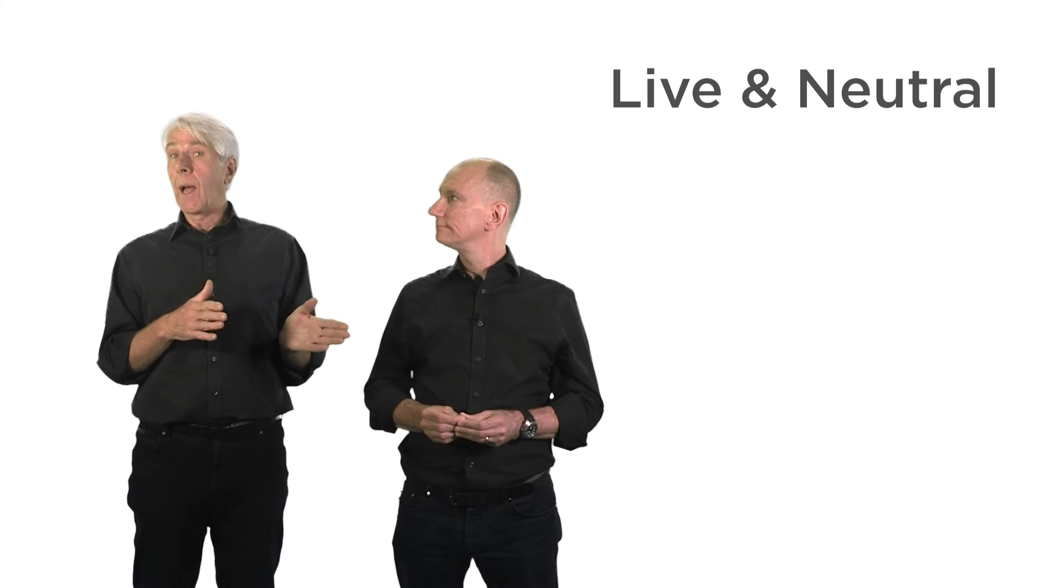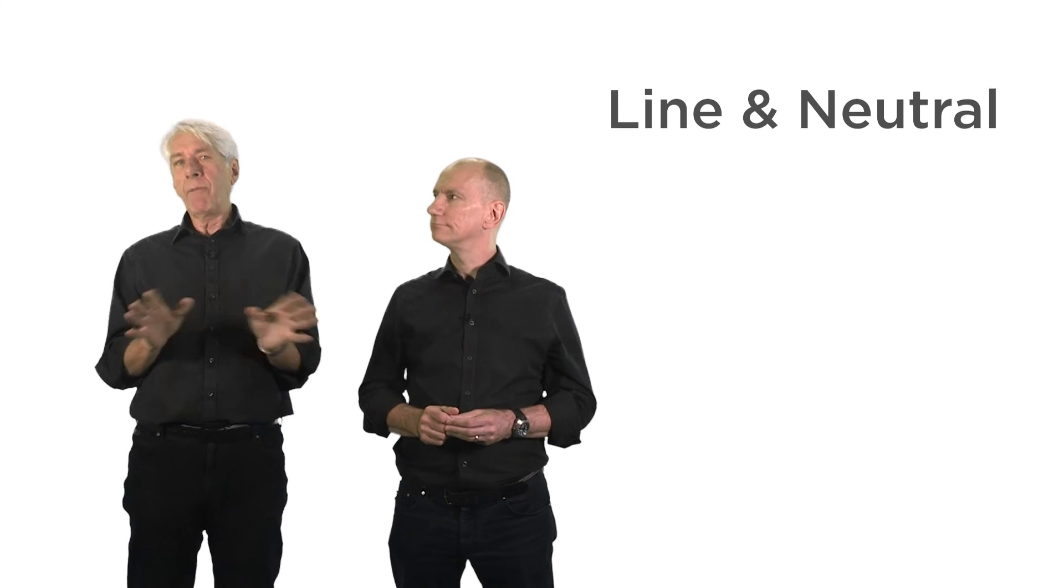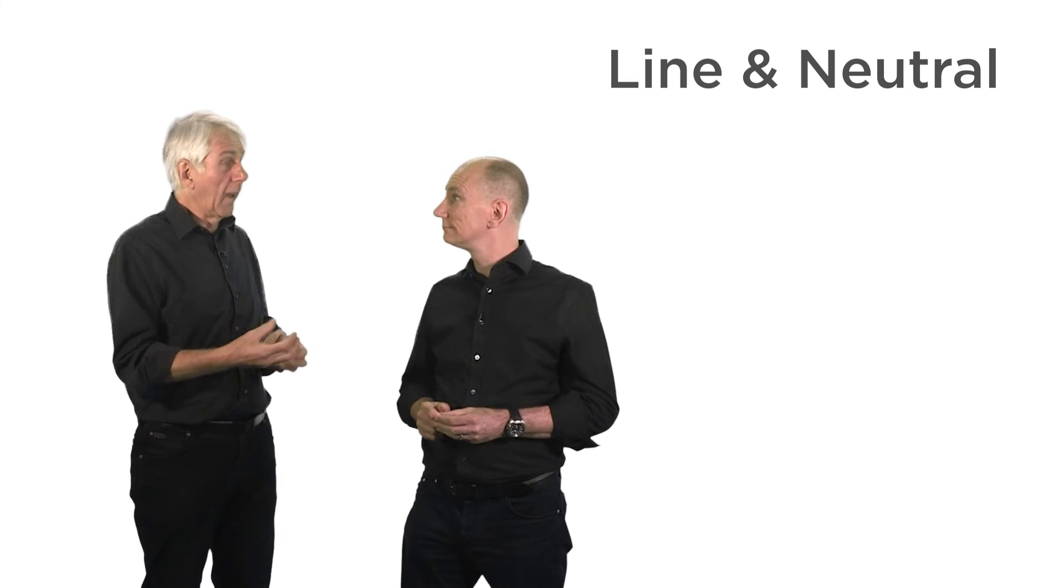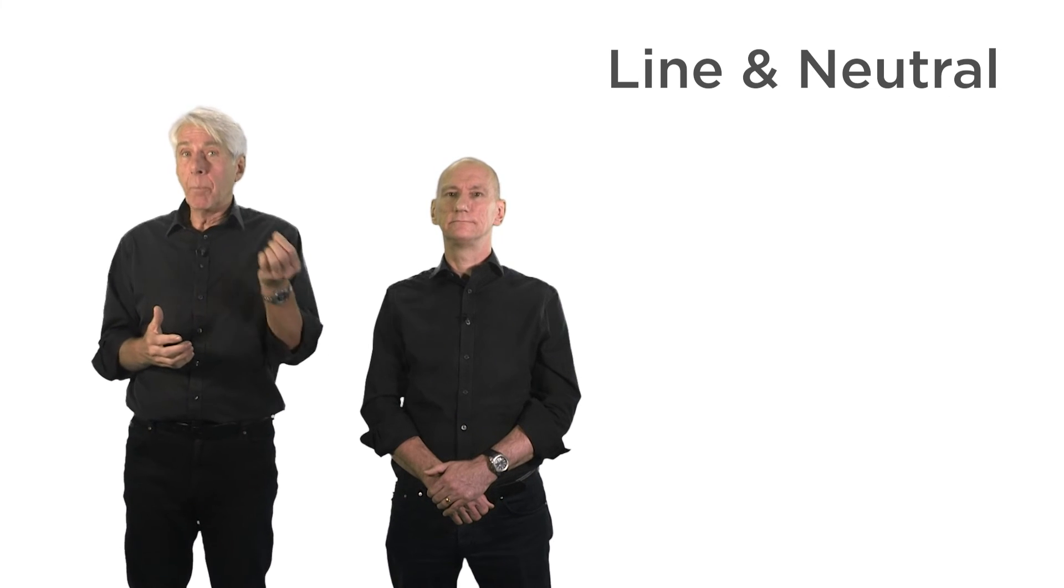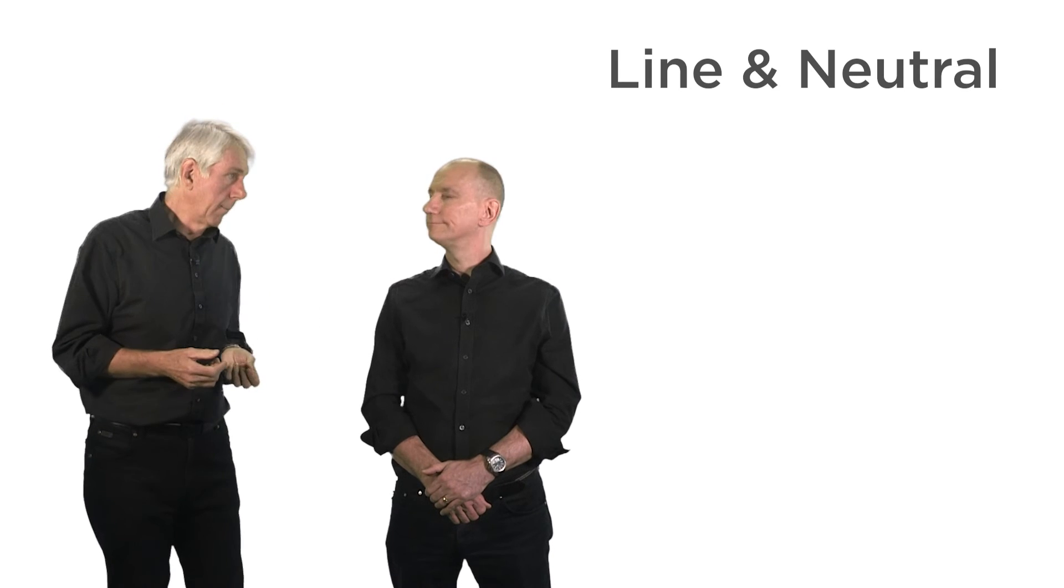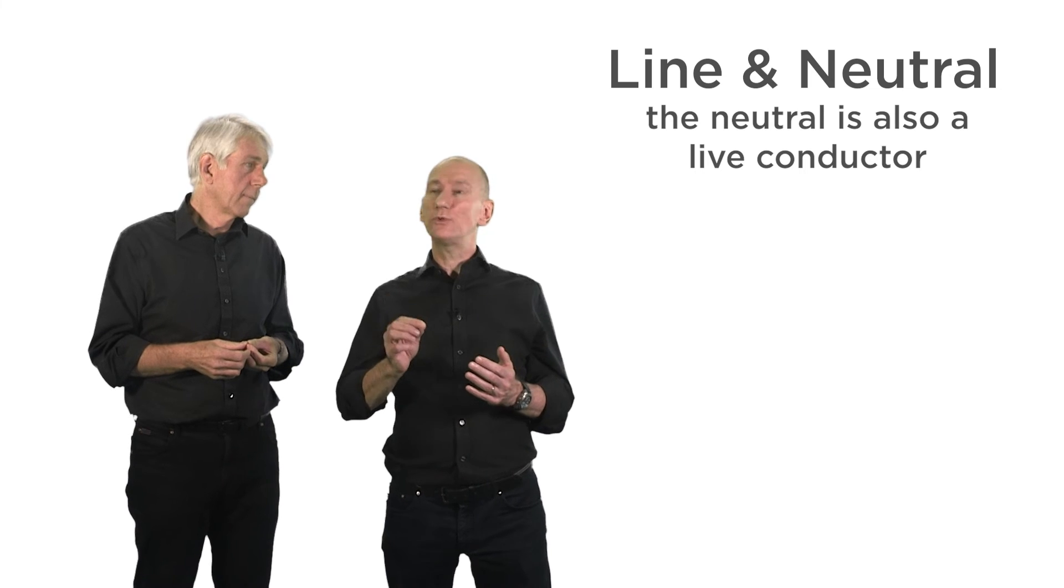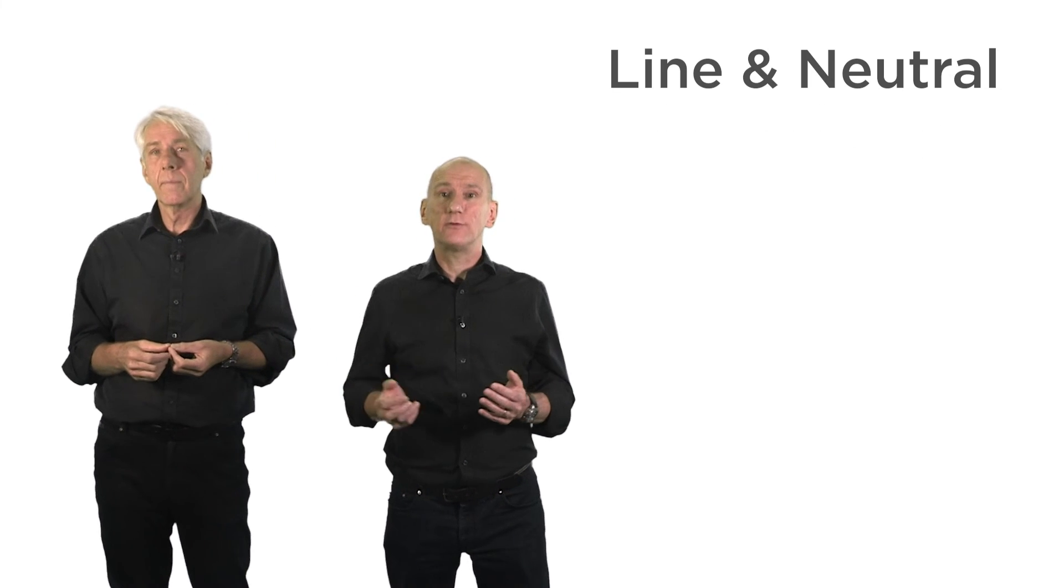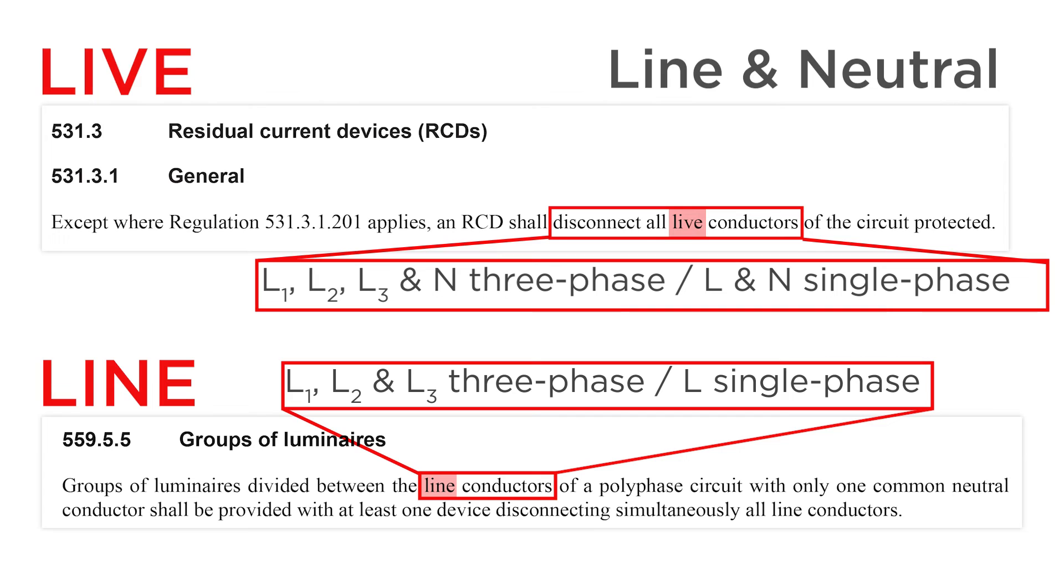The next term is live and neutral where the correct term is in fact line and neutral. Now I think we should cut everyone some slack here as the Regs only introduced the word live about 100 years ago or so. But joking aside, over the years references to L have changed to P for phase and now is currently L again. Yes that's true but at least it's logical. The reason is that neutral is also defined as a live conductor. So that helps us avoid ambiguity, especially when a regulation states for example all live conductors must be disconnected from the supply. That means all lines and the neutral of a three phase supply, and in the case of a single phase supply that's L and N.